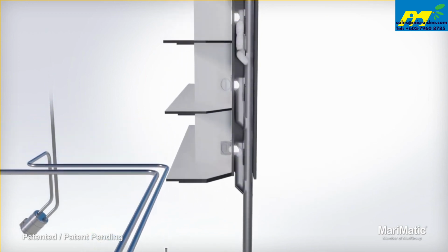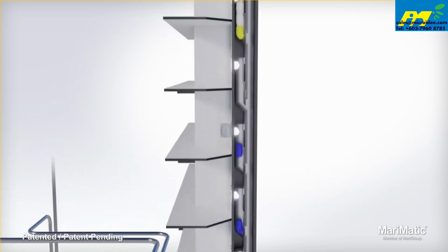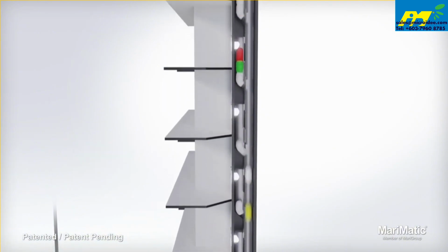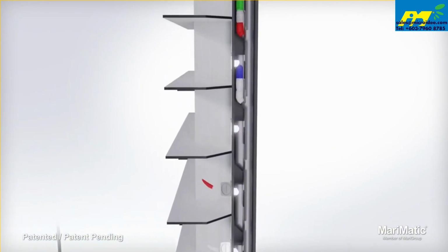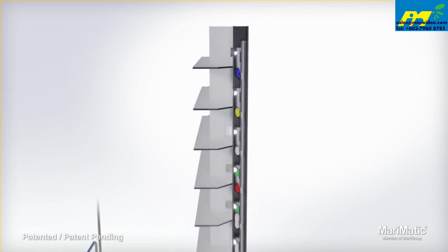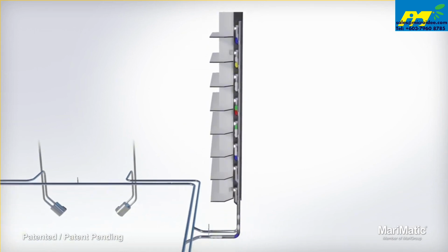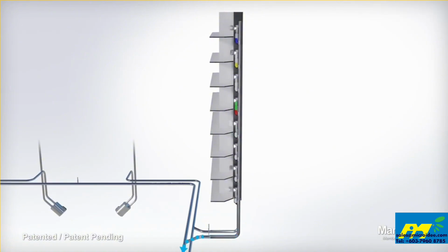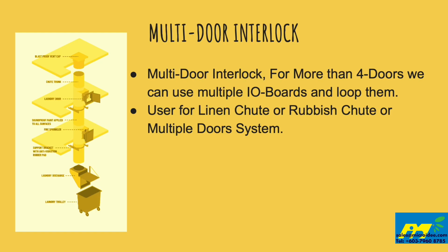Since there are more than 4 floors in a tall building, we use multi-door interlock to lock all the chute doors. You add multiple I/O boards that can communicate with each other to make it a multi-door locking system. Multi-door is used when more interlock doors are needed than the board itself can support. So we use multiple boards that can communicate with each other to achieve this scenario.